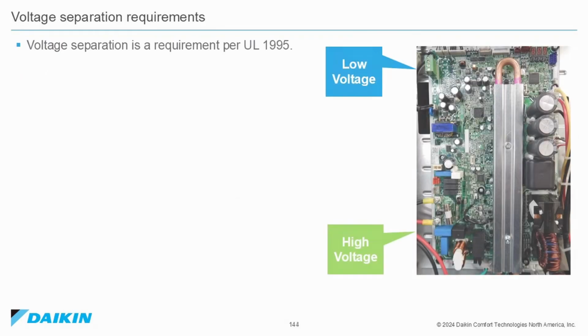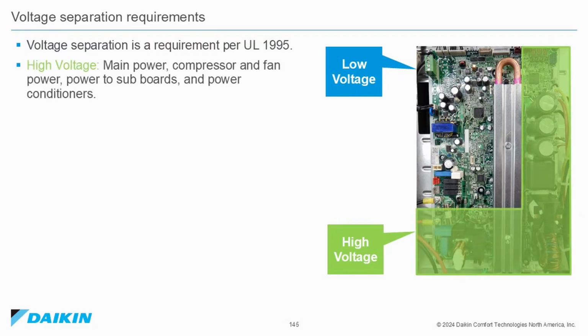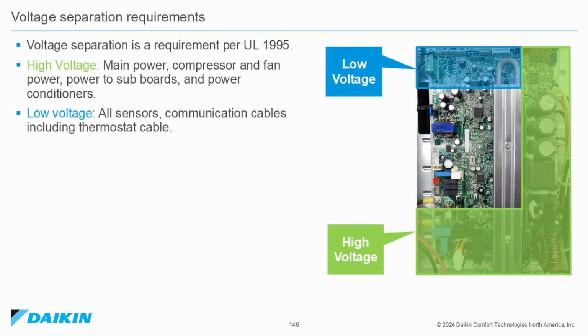Voltage separation requirements. Voltage separation is a requirement per UL 1995. High voltage, which is main power, compressor and fan power, power to sub-boards, and power conditioners. Low voltage is all sensors, communication cables, including thermostat cable.